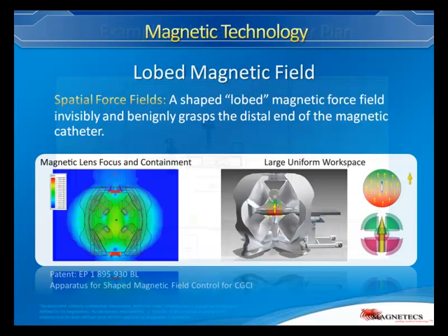Next. The important part, as I said, is that I will concentrate on only one element of the system. We call that lobed magnetic field. And regarding the entire efficiency of the system, I just want to mention that when we originally brought this concept to the most notable specialists at the General Electric MRI unit, all of them specialists in magnetics with the highest acclaim, they basically said it's impossible and the power requirement would be around 400,000 watts. We operate normally at around 36,000 watts, so you can see that it's an order of magnitude below that.